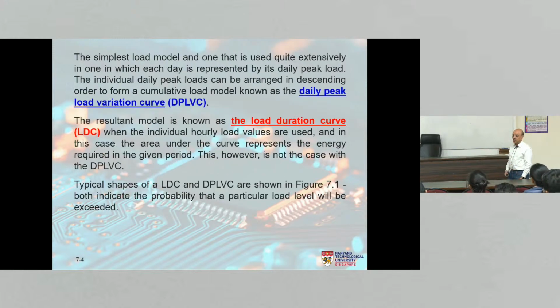There are two models that are commonly used. Both are sort of related, but one of them deals with the daily peak load. You know, Monday, the peak load is this much. Tuesday, the peak load is this much. You don't consider the load hour by hour. You take just the maximum load on a particular day, and we use that. Then we arrange them in chronological order, in descending order, and that curve is called the daily peak load variation curve. The other curve is the load duration curve. The load duration curve takes the hourly loads and arranges them in descending order. So one deals with hourly loads, the other deals with daily loads, right?